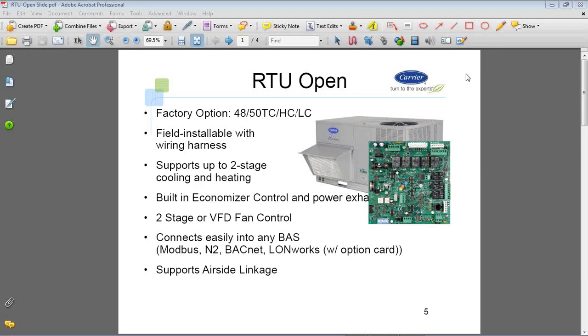So the Carrier RTU Open Controller is a Bacnet native DDC controller that is used to control small packaged Carrier rooftop units. Now I say Carrier, but it can also be used to control any small packaged rooftop unit. It can control Trane, York, anything that has a thermostat terminal board. When talking about Carrier rooftop units, it would be the product line, the 48/50 TC, HC, or LC, going up to 28.5 tons. And you can get these controllers factory installed. That would be something you talk to your salesman about.